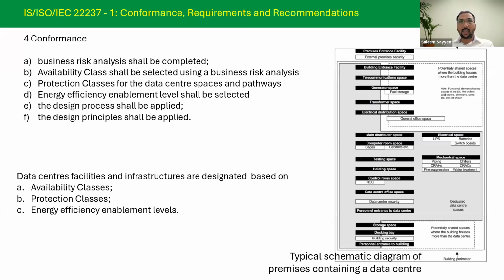Now, if you see a data center nowadays, we used to hear 1 megawatt, 2 megawatt, maybe around 5 to 10 years back. Right now, data centers are in double digits, 70, 80, 100, 99, such kind of figures are coming up. So energy efficiency plays a very, very important role. We have to see how we can improve the PUE. So PUE, power usage effectiveness, where the losses in your transformer, your distribution, and also at your cooling play a very, very important role. While designing a data center, efficiency has to be taken care of in a very, very optimized way.